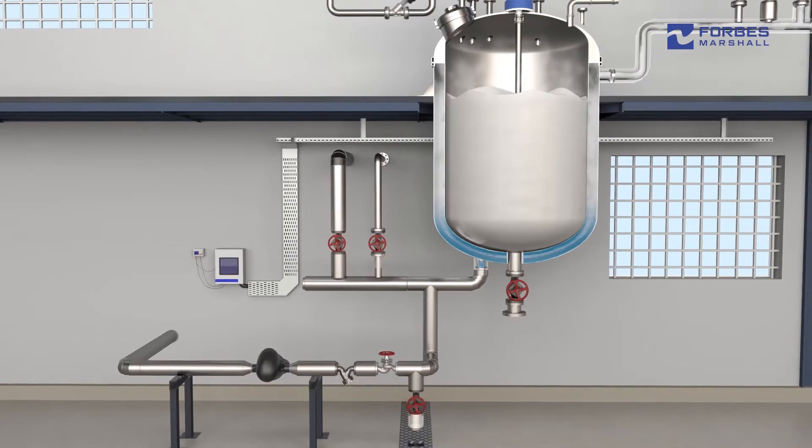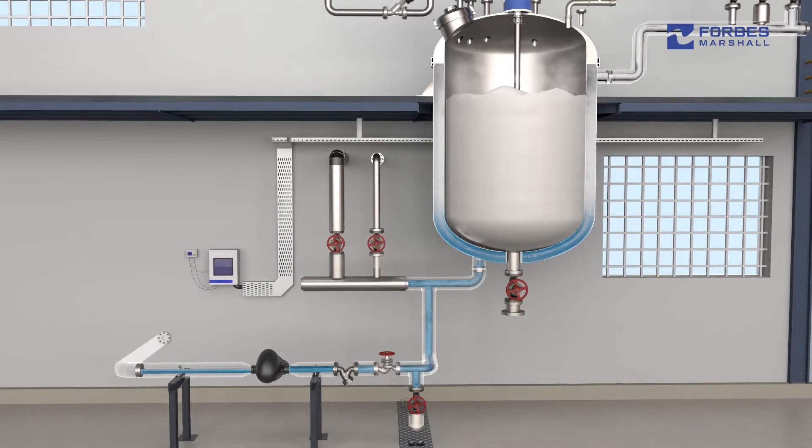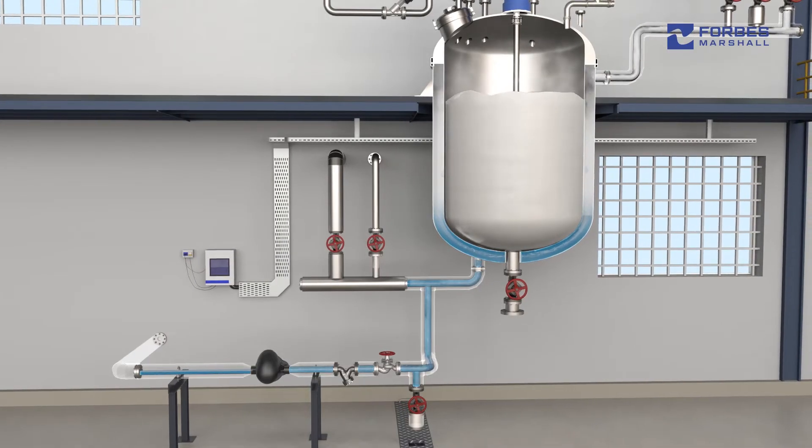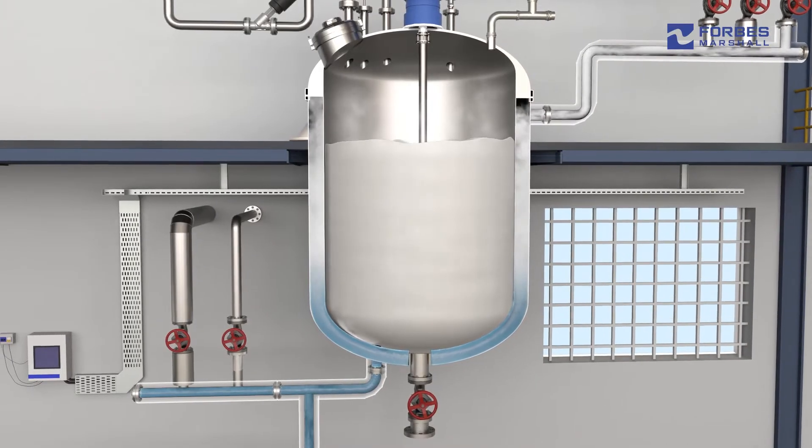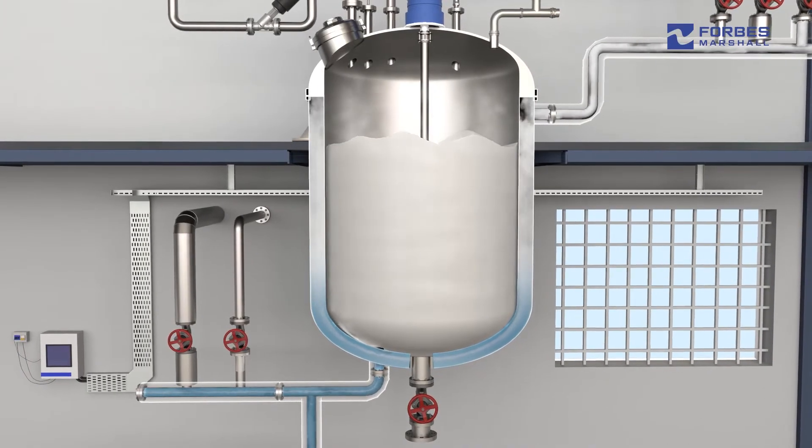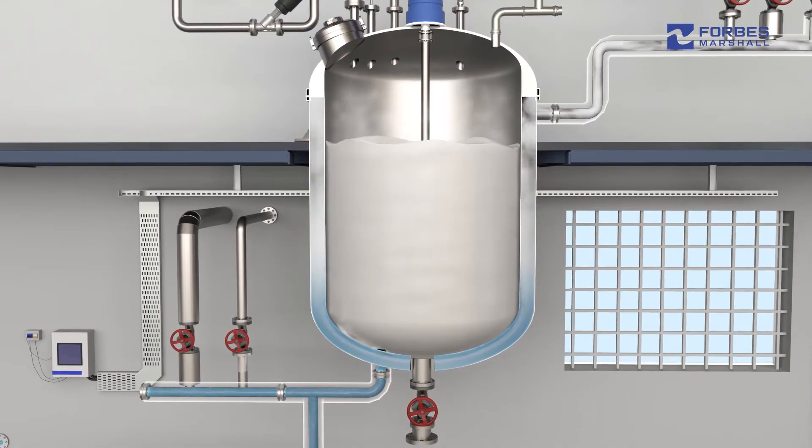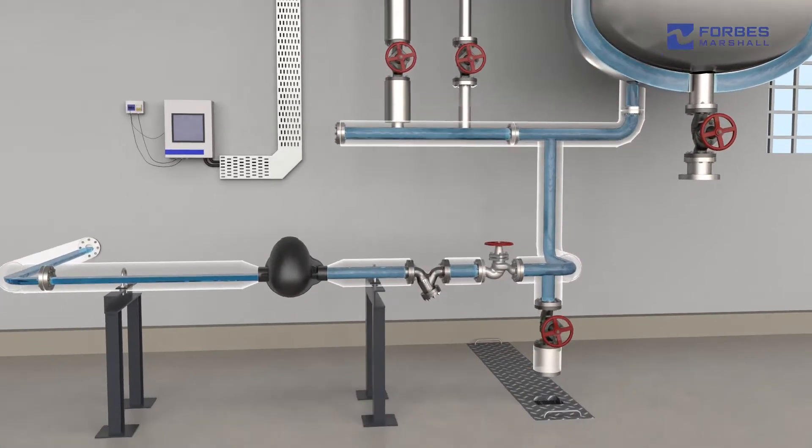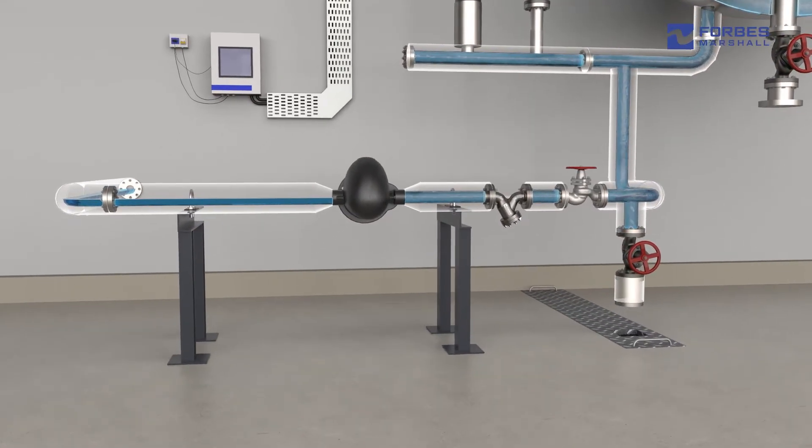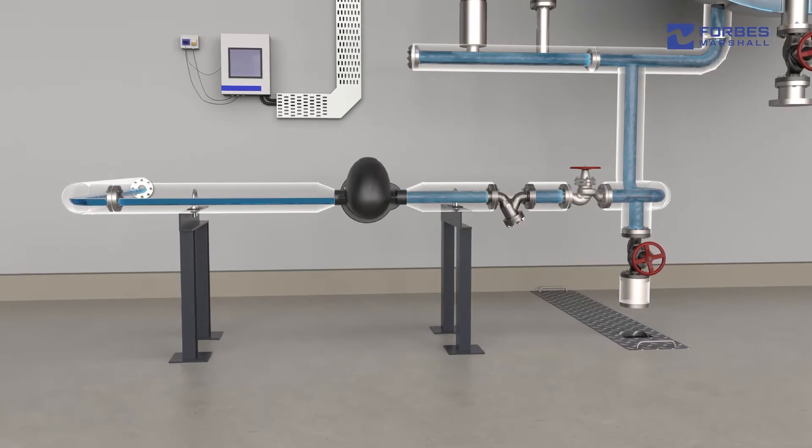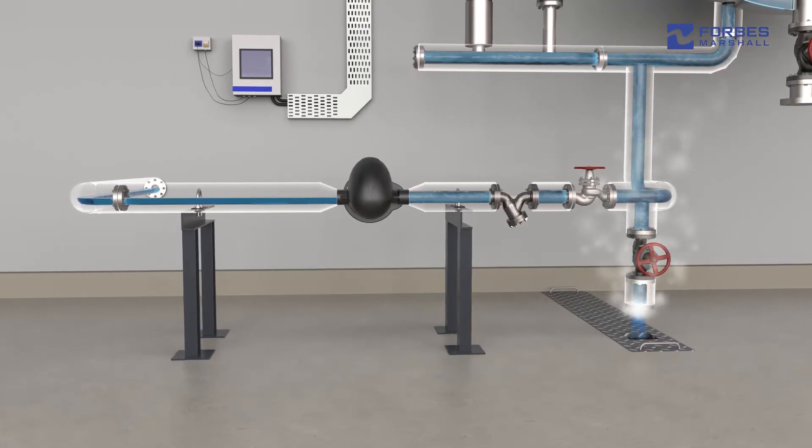Condensate which gets contaminated during changeovers is drained to the ETP or cooling tower. Steam load for these batch processes is significantly higher at startup. Conventional traps are not able to completely evacuate condensate and need to be bypassed, leading to steam loss.